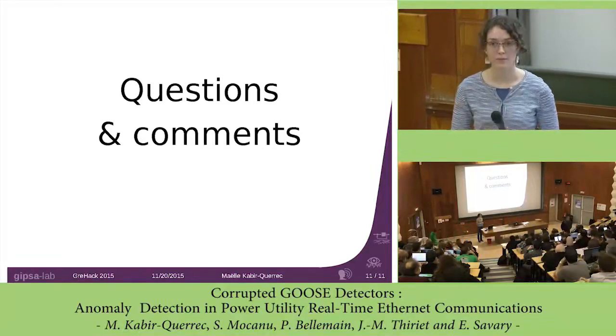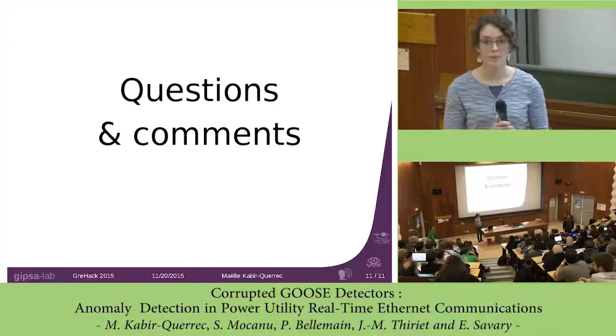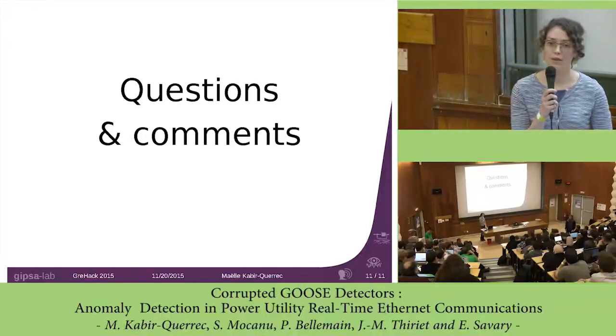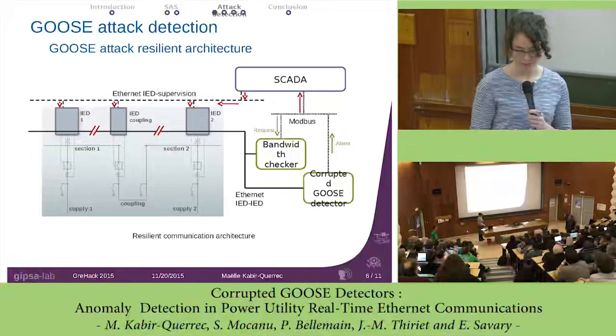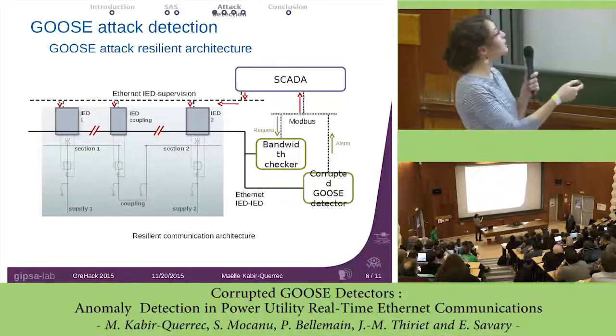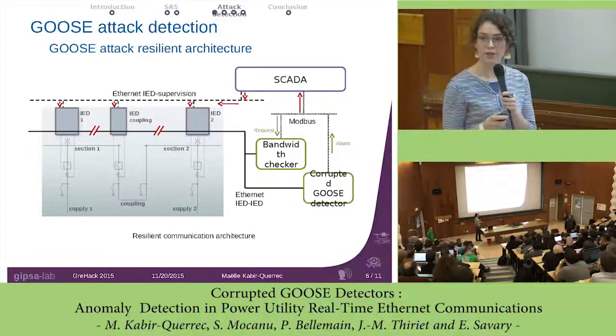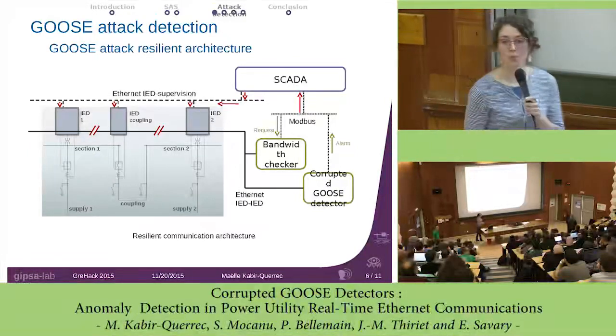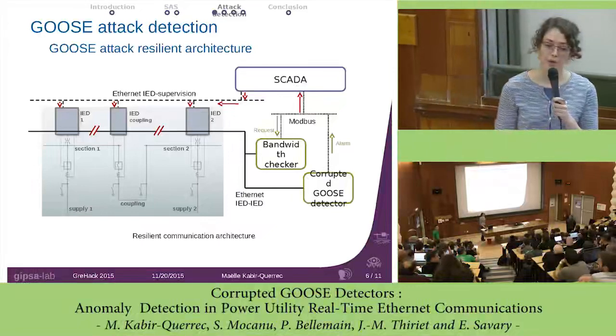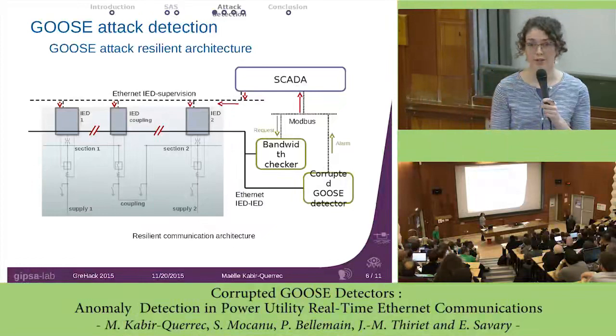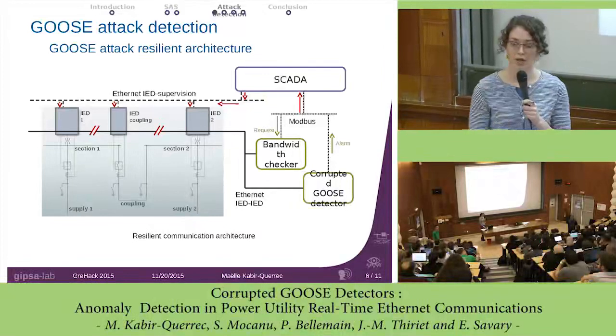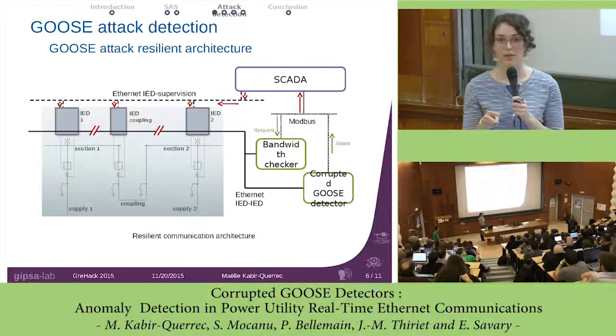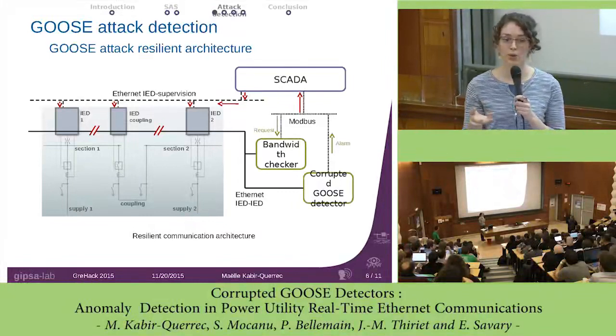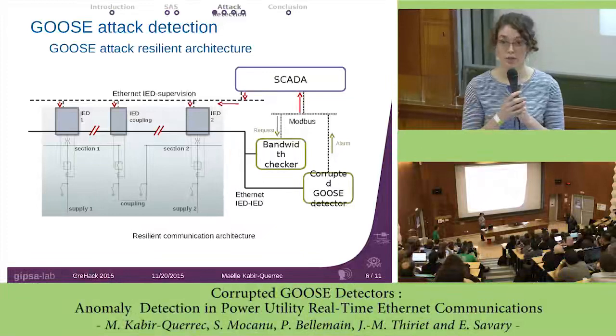How do you stop the GOOSE communication after the attack is detected? How do we stop it? What do you mean? You mean how do you block it? Here, yeah. When I say that I prevent IEDs from communicating with each other, it's in the program. You can program logic into those devices, and so when they receive the alarm from the supervision, they will switch programs, and in the new program they will execute, there is no involvement of GOOSE messaging. That's it. Thank you.